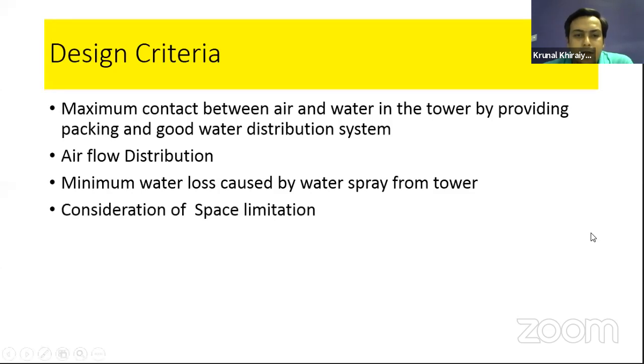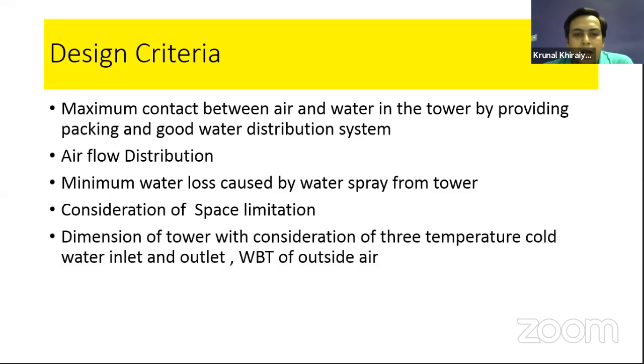Then considerations of space limitation. Yes, a very important design aspect. Then the dimensions of the tower, with consideration of the three things: what temperature the water is coming into the cooling tower, what temperature you need to supply it at again, as well as the outside air conditions, meaning the WBT of outside air. These are the three important criteria, and with respect to these you need to design your tower. And last, very important, the quality of the water or fluid which is available as the cooling medium.